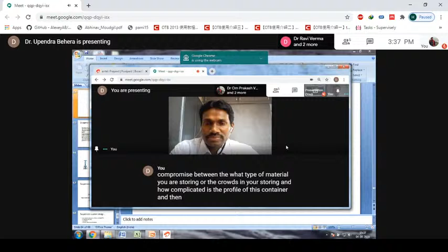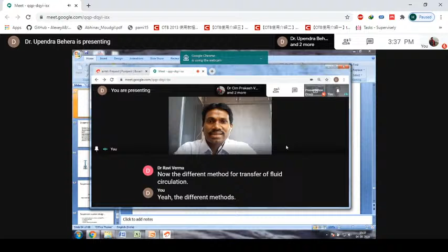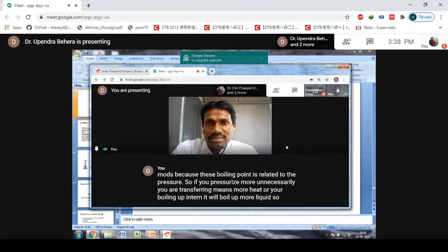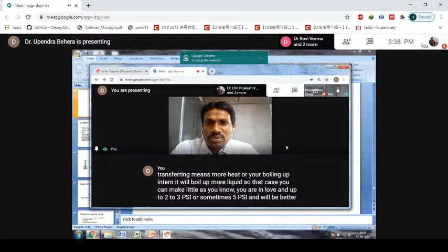Okay. So one question is, sir, what are the different methods for transferring cryogenic fluid? Yeah, as I have told, there are three different methods for transferring this. You can do self-pressurization. Even for liquid helium, you can pressurize a little and then take out the liquid. But one should not pressurize much because the boiling point is related to the pressure. If you pressurize more unnecessarily, you are transferring more heat, or you are boiling up, which in turn will boil up more liquid. So in the lab, up to 2 to 3 psi, or sometimes 5 psi, is required to transfer even a good quantity of liquid helium.